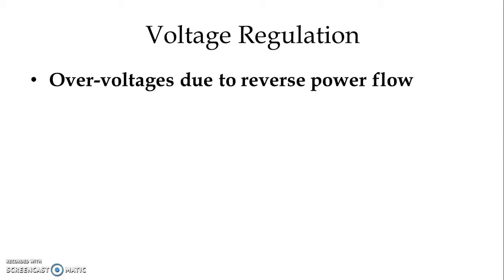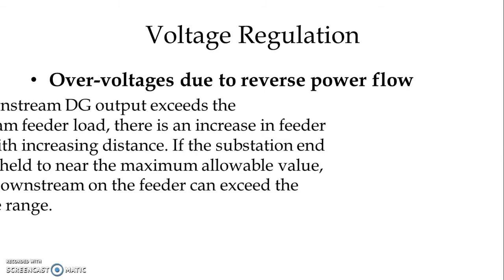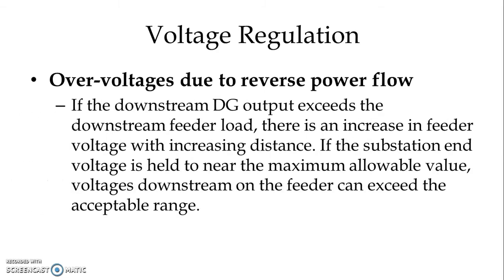One of the issues is over-voltage due to reverse power flow. If the downstream DG output exceeds the downstream feeder load, there is an increase in feeder voltage with increasing distance. If the substation end voltage is held to near the maximum allowable value, voltage downstream on the feeder can exceed the acceptable range.